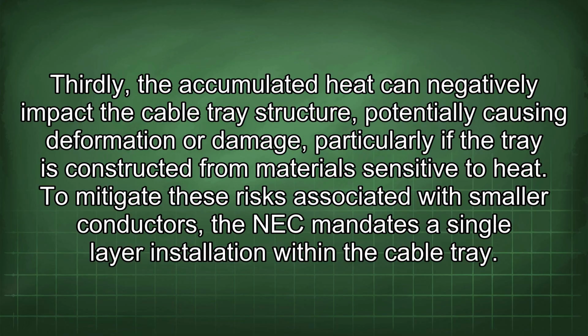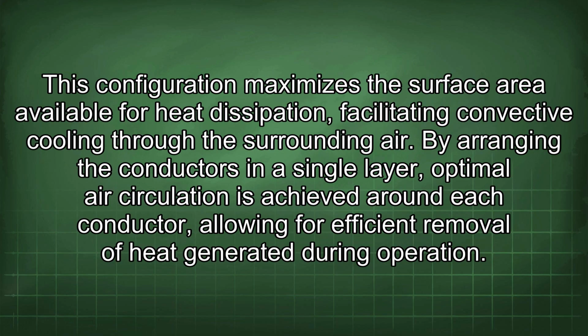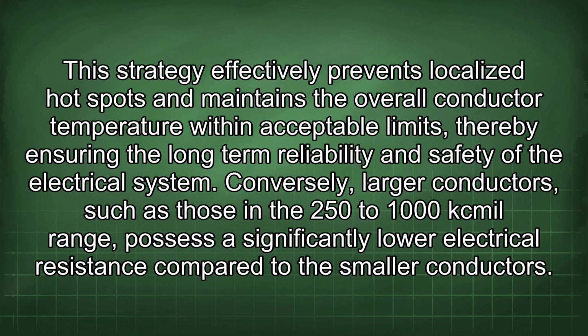To mitigate these risks associated with smaller conductors, the NEC mandates a single-layer installation within the cable tray. This configuration maximizes the surface area available for heat dissipation, facilitating convective cooling through the surrounding air. By arranging the conductors in a single layer, optimal air circulation is achieved around each conductor, allowing for efficient removal of heat generated during operation. This strategy effectively prevents localized hotspots and maintains the overall conductor temperature within acceptable limits, thereby ensuring the long-term reliability and safety of the electrical system.